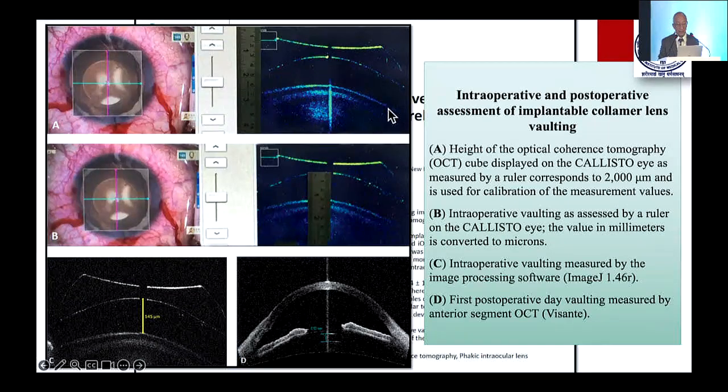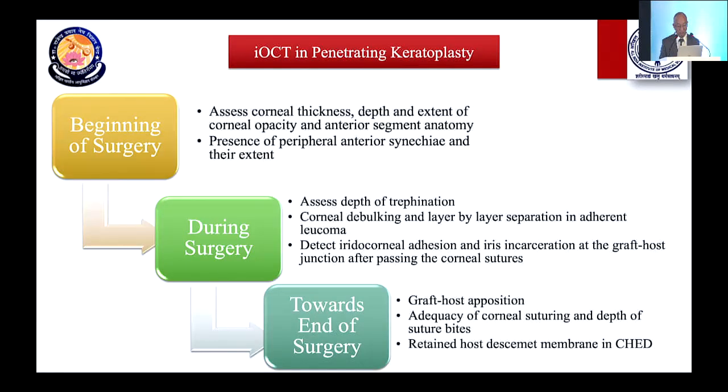This OCT doesn't have the micrometer caliper. So we designed the magnification factor. We could calibrate it with a ruler also. And the next day we compared the OCT pixelization, it was matching. And this device, where you can calculate the thickness of a tissue or the depth of a tissue in microns, gives you a good assessment of all the structures also.